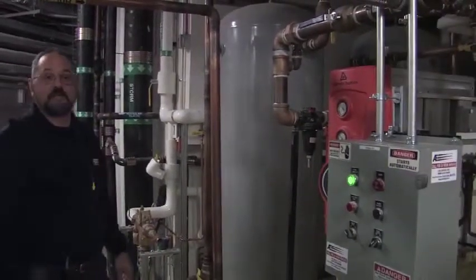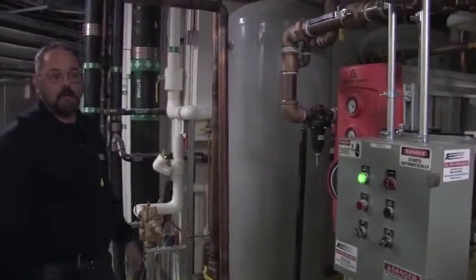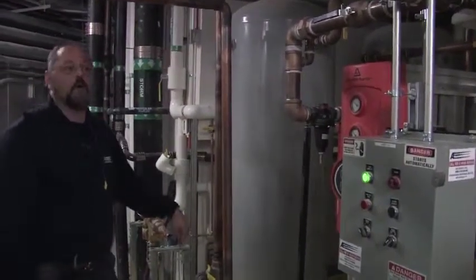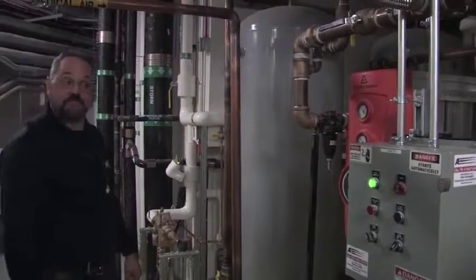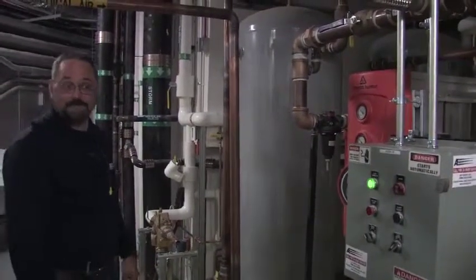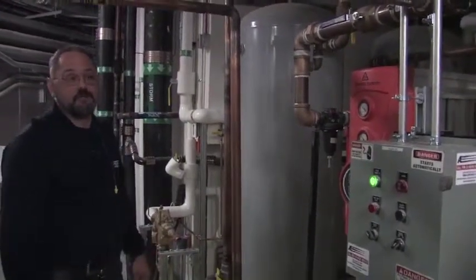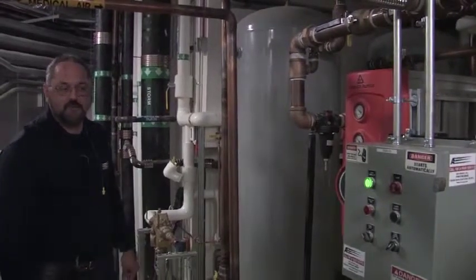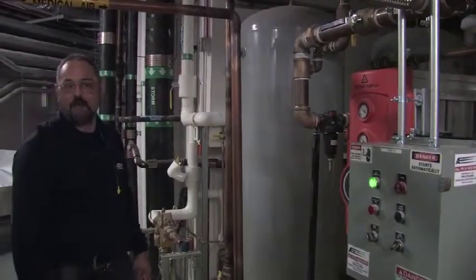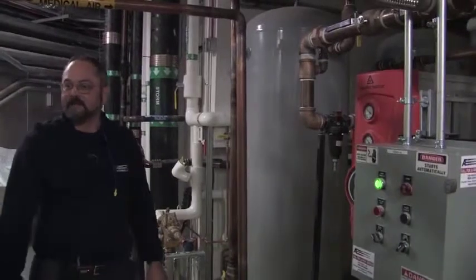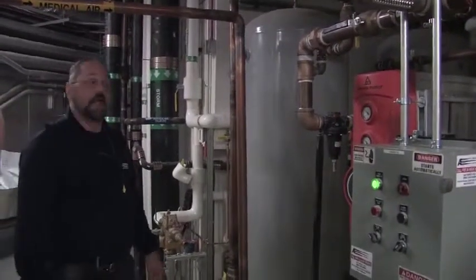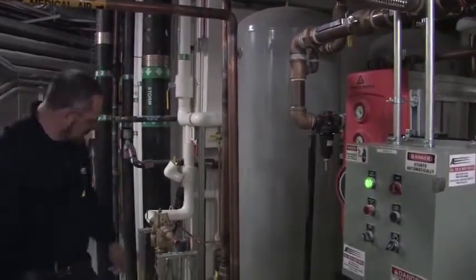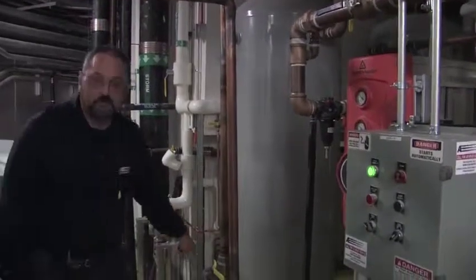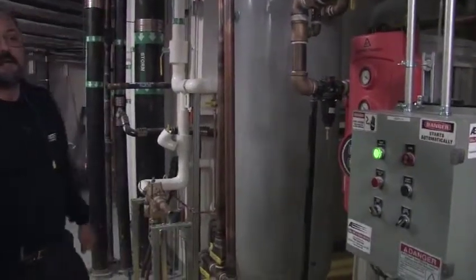The other amazing thing is it was on a level where there were two more floors below it. So the interesting thing is the floor held. Yeah, that's a lot of weight. It's a 3,000 gallon tank. I guarantee they had at least 2,000 gallons at 8 1/3 pounds a gallon in that tank. That is a lot of weight. So always good to have the manual drain line and check it.